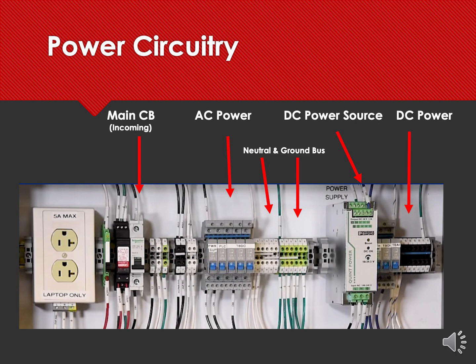Moving to the right, you'll see the DC power source. This acts as both a transformer and a rectifier. What it does is it converts the 120 volts down to 24 volt DC power, and immediately to the right of that are the circuit breakers and the grounding bus, and the equipment grounding bus for the DC side of the panel. The DC side represents very little shock or arc flash hazards in this particular panel, but once again, the qualified worker requirements will stipulate that they must be trained to recognize where the hazards are significant and where they aren't. And in this particular panel, it's fairly low arc flash hazards, but significant shock hazards on the AC side of the panel. Let's go to the next slide.